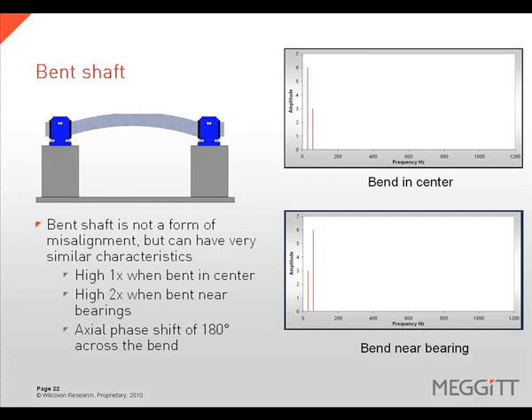A bent shaft can exhibit either a high 1x or a high 2x depending on the location of the bend in relation to the support structure. If the bend is close to one of the supports or bearings, 2x vibration will likely be dominant. If the bend is farther from the supports or centered between them, 1x rotational speed will likely be predominant. With misalignment, the phase shift is across the coupling, whereas with a bent shaft the phase shift will occur across the bent portion of the shaft, with a 180 degree phase shift expected in the axial direction.